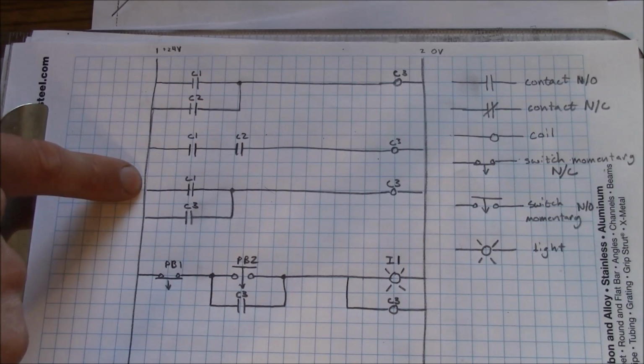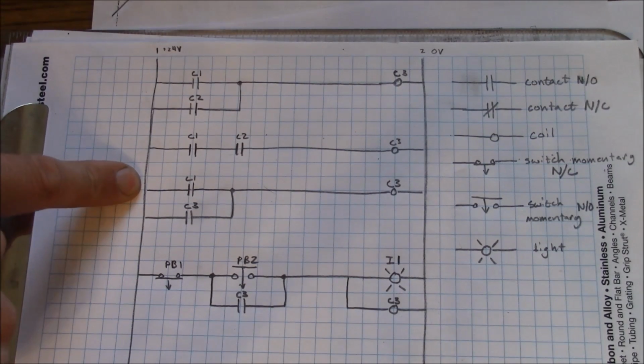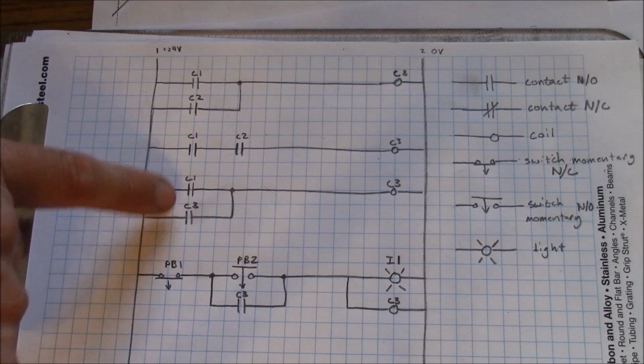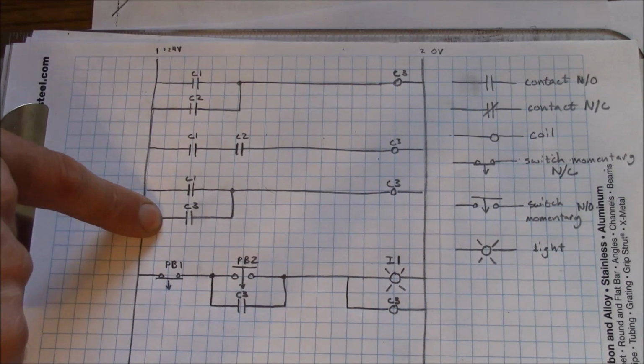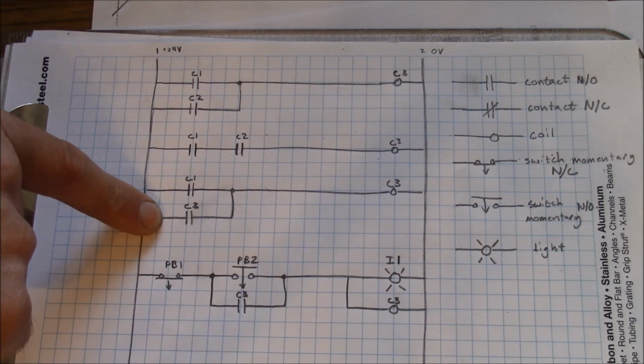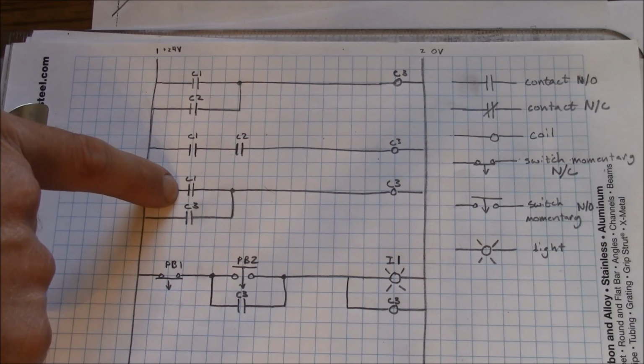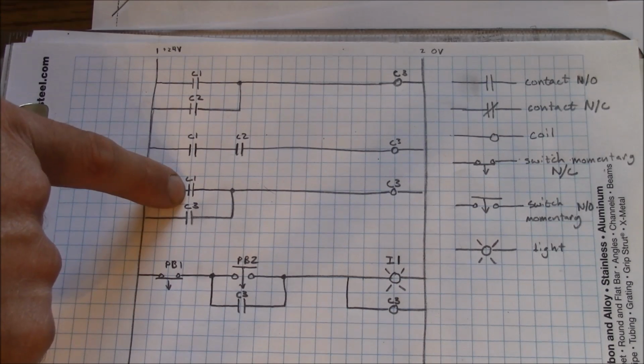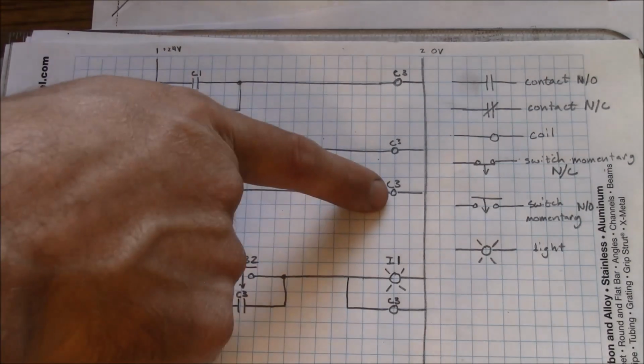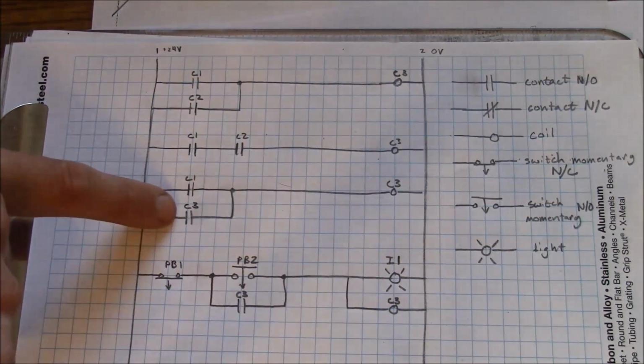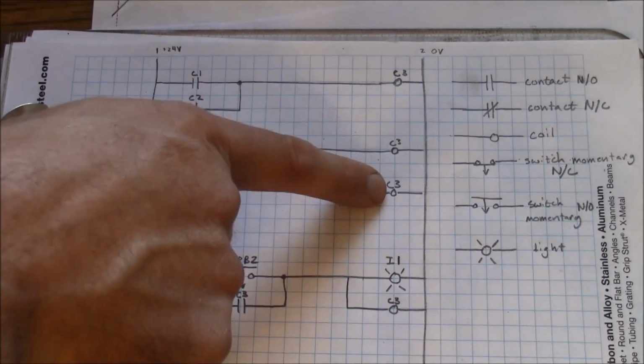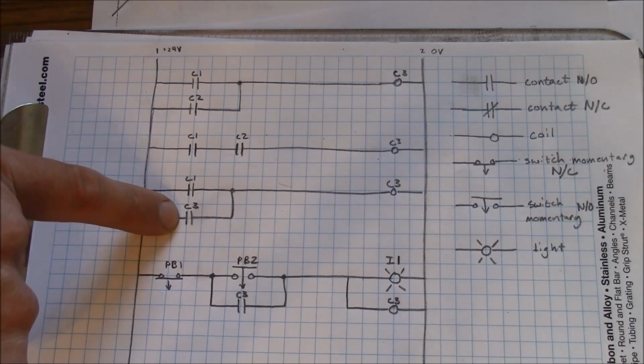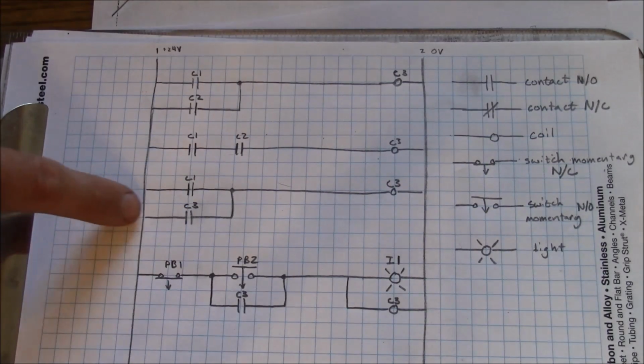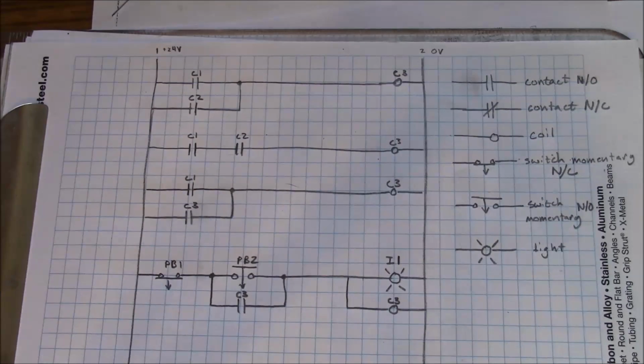Now this next circuit is extremely common in machine tools. This is a parallel circuit, so it's an OR, but this is what's called a latching relay. When C1 contact closes, it energizes C3, and this is the contact from C3. So whenever C3 coil is energized, contact C3 is closed, meaning it's self-powering, or latching.